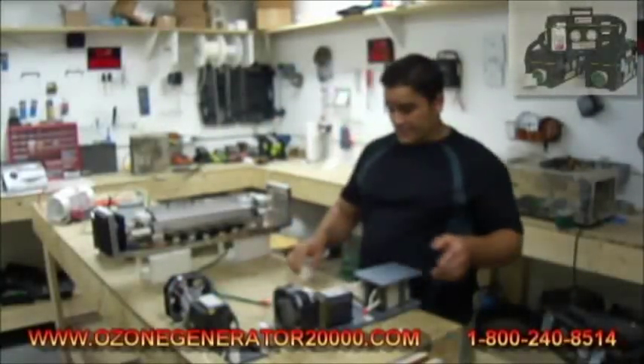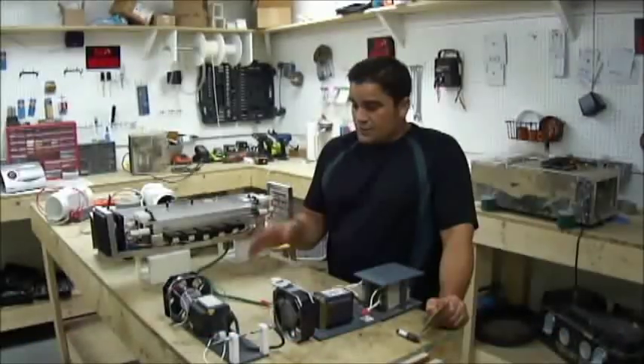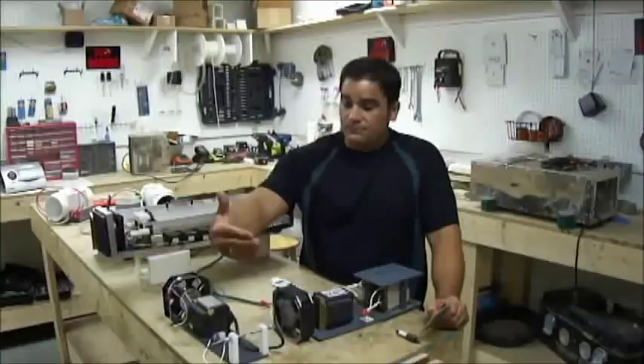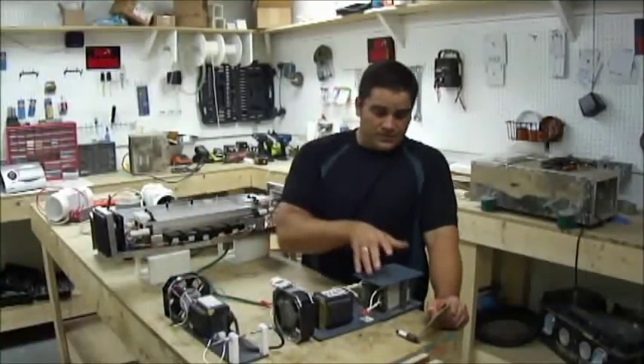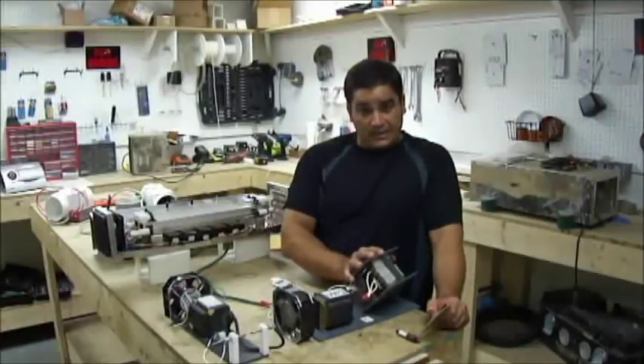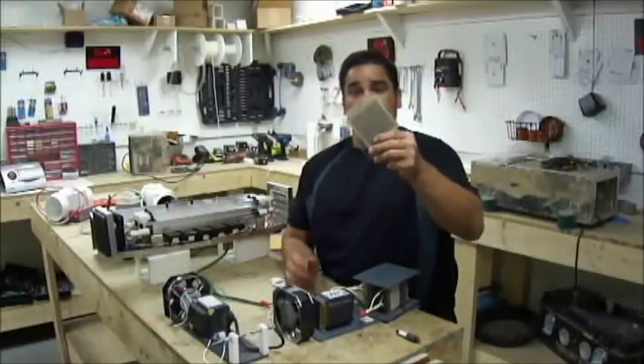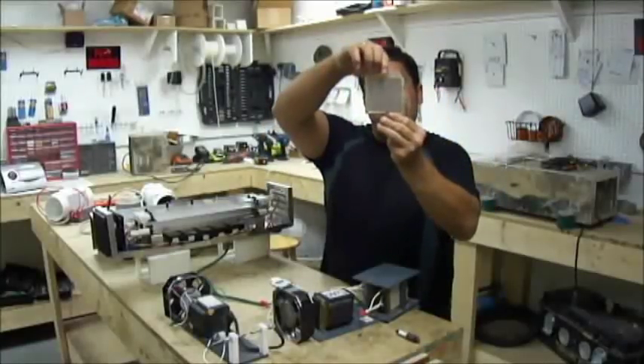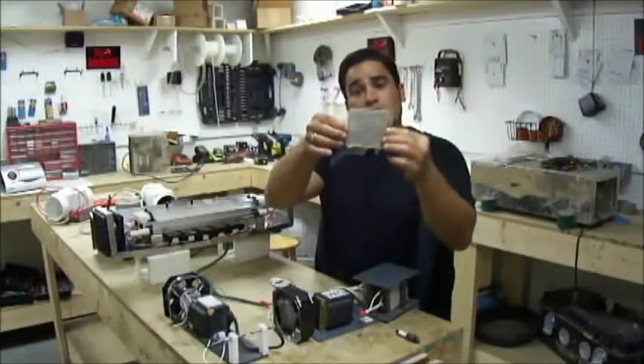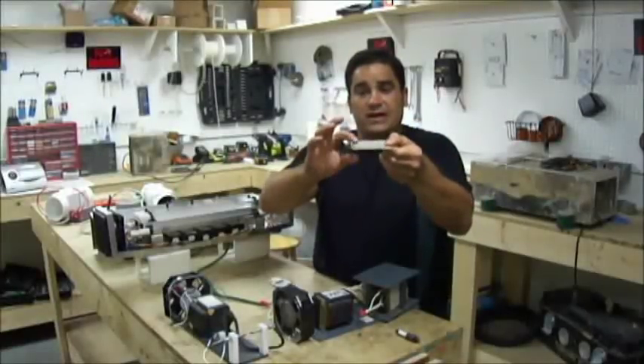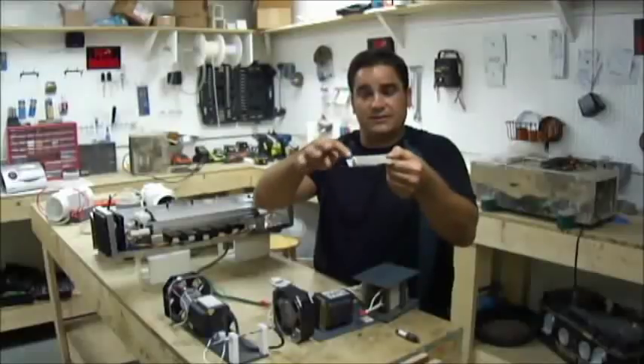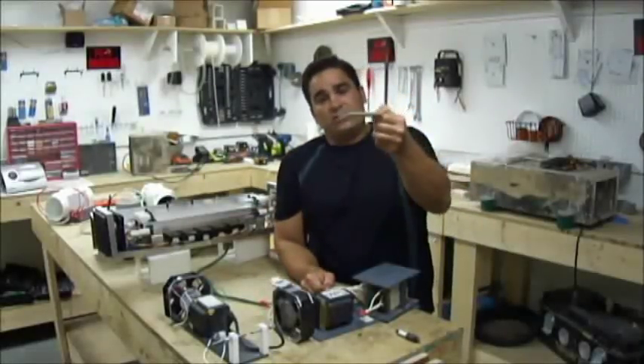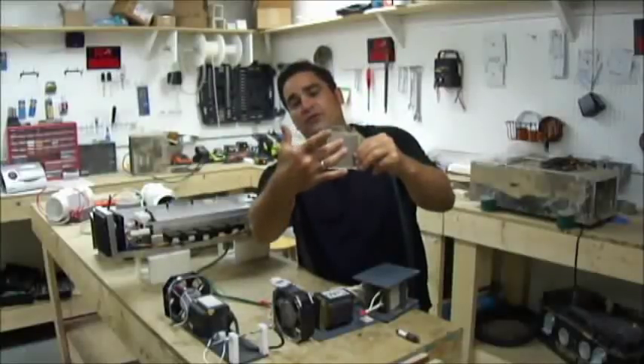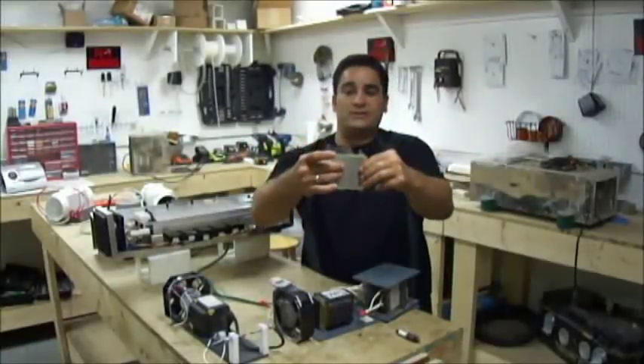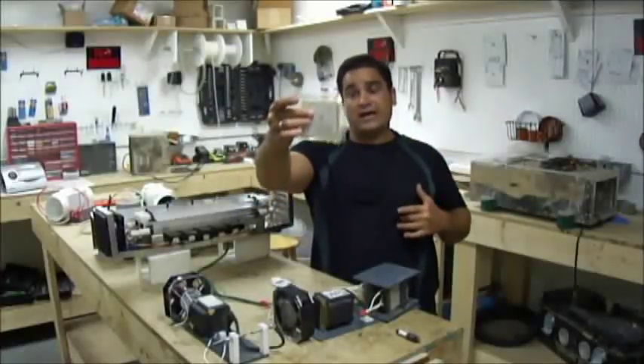I'm going to turn this off, and then we're going to show you some various other types of ozone generating equipment. So we've talked about the basic air gap or spark gap ozone method. We've talked about mica being used as a dielectric. Here's another popular dielectric media. I don't know if you can see this. This is a thin piece of what's called borosilicate glass. It has sharp edges because it's broken over time. And on either side of the borosilicate glass is a piece of stainless steel that's glued down around the edge. And in the ozone machine, this thing gets inserted. High voltage current will be passed on one side and the ground on the other side. And in between, the glass forms the dielectric media.